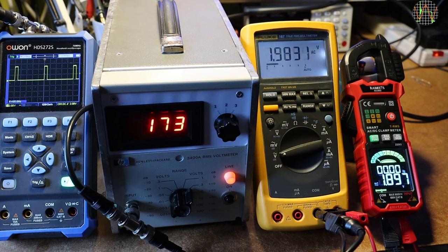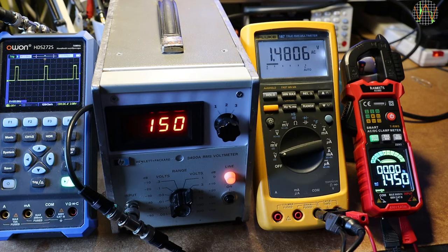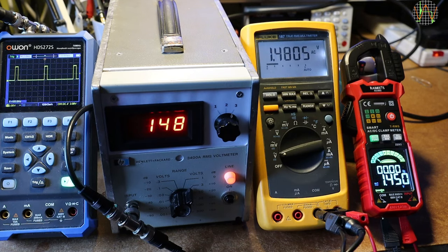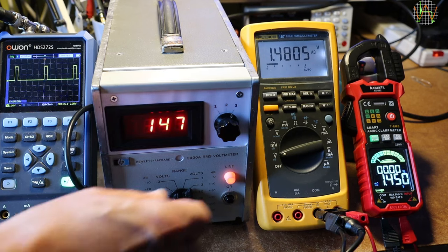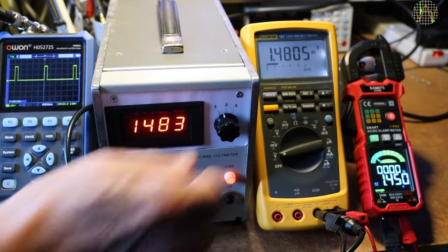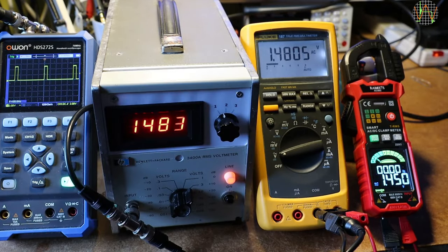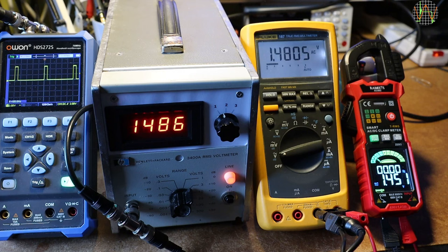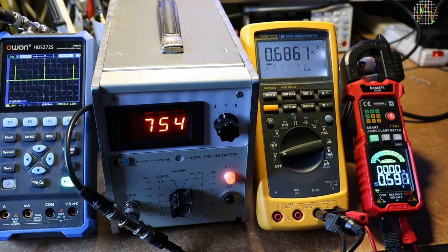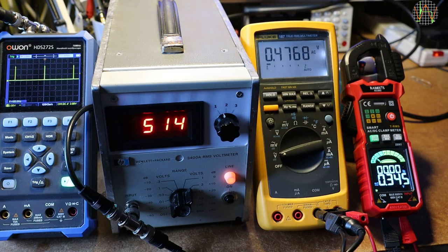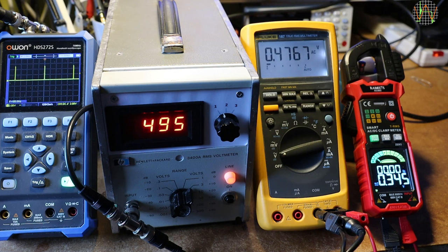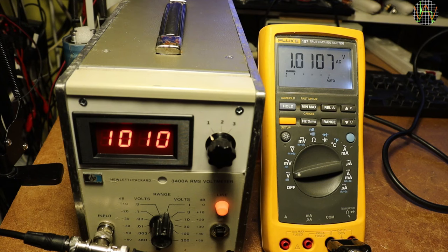Reducing the duty cycle to 10%, which means a crest factor of 3.16 and the value on the clamp meter is now notably lower than the Fluke and the HP3400A. Reducing the duty cycle further to 1% or a crest factor of 10 and now there is a small error in the Fluke, but the clamp meter is quite significantly lower than it should be.